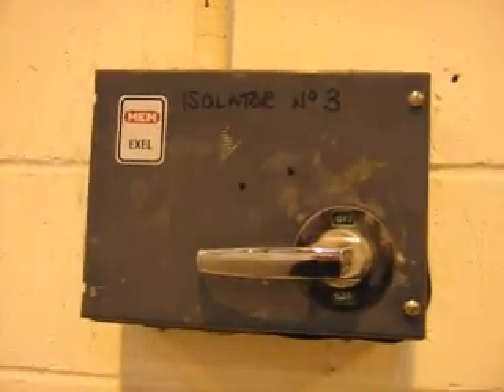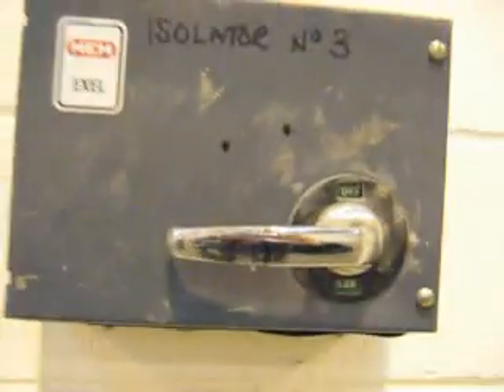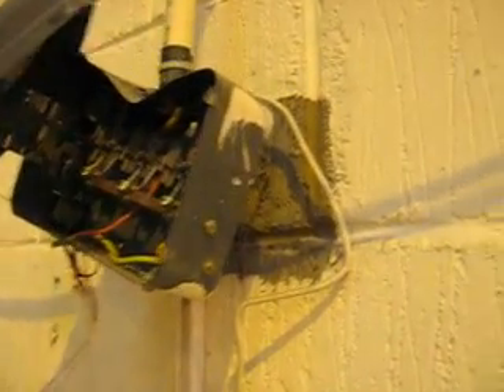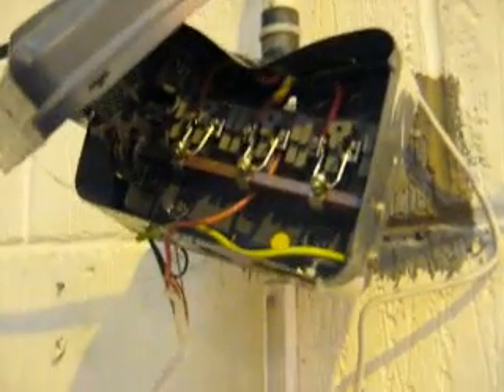Many of these disconnectors, labelled up as isolators, are doing nothing. Presumably at one point in their life they supplied a machine, but now they're doing nothing. And the underside indicates that at one point there was a conduit coming out the bottom, so they're actually doing nothing at the moment. Smashed up three-phase switch. At the moment it's dead, but that doesn't mean it can't be energised simply by throwing a switch, so quite dangerous. Underneath it is a lash-up connection to a 13 amp socket.